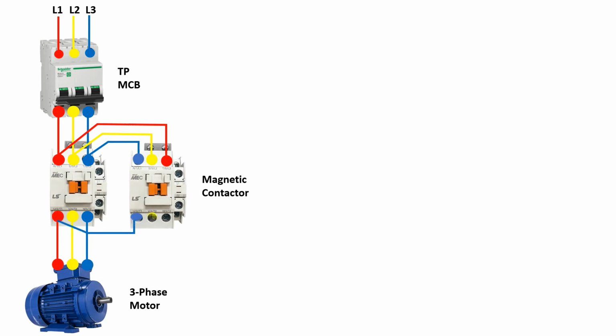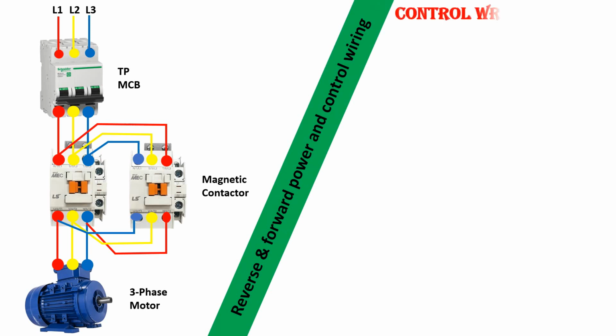For the control wiring, connect the power supply to the circuit breaker for overcurrent protection. From the circuit breaker, wire to the emergency stop button. This button should be normally closed and placed in series with the power supply to enable quick power cutoff in emergencies. Wire from the emergency stop button to the selector switch.